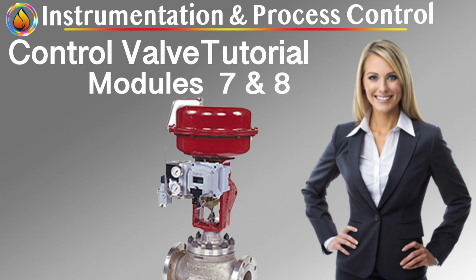Dynamic performance. Dynamic performance defines how fast and how cleanly a valve responds to change. Response time T63. T63 is the time required for the valve to reach 63% of its final position following a step change in input. Why T63 matters: it represents effective valve bandwidth, it correlates directly with achievable loop speed, and it defines how much controller gain can be applied safely. A valve with slow T63 forces conservative tuning even if the process itself is fast.